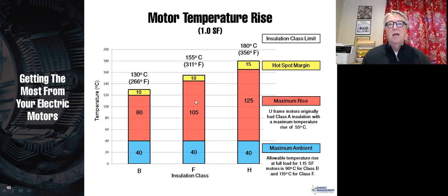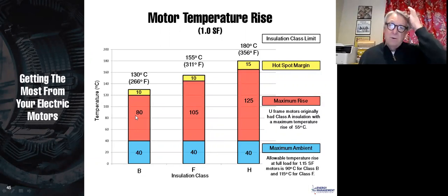Class F insulation is 155 degrees, and it allows you 105 degrees rise then. Now the question is, what should we do with that? We could do 2 things with that. We could either provide a motor that has Class F insulation and is rated for a Class F rise, meaning the manufacturer expects that motor to be running at 155 degrees C when it's at full load. Or we could say, no, we want a motor that has Class F insulation, but it only runs at 80 degrees C rise. Why would we do that?